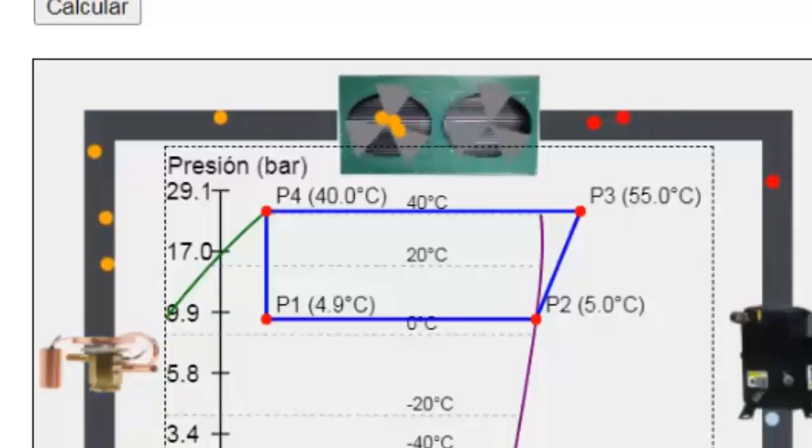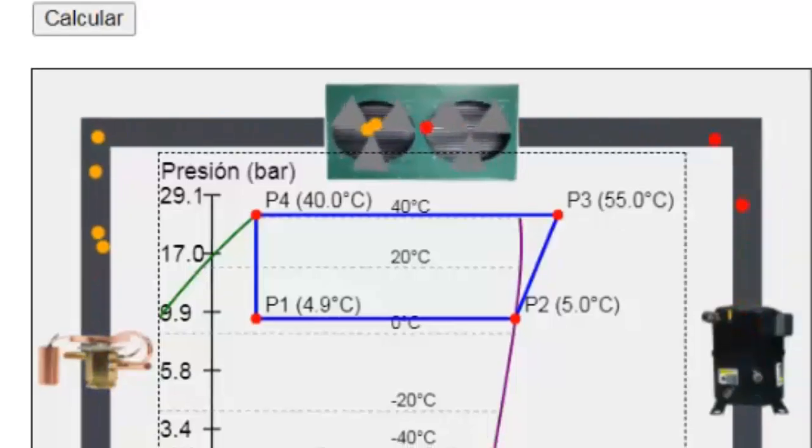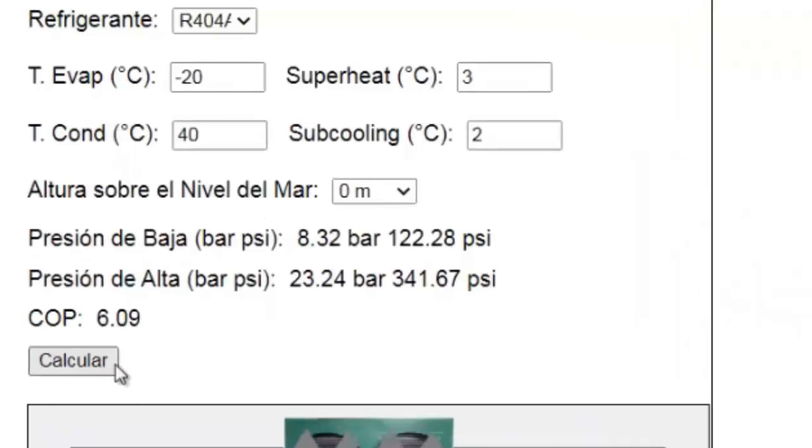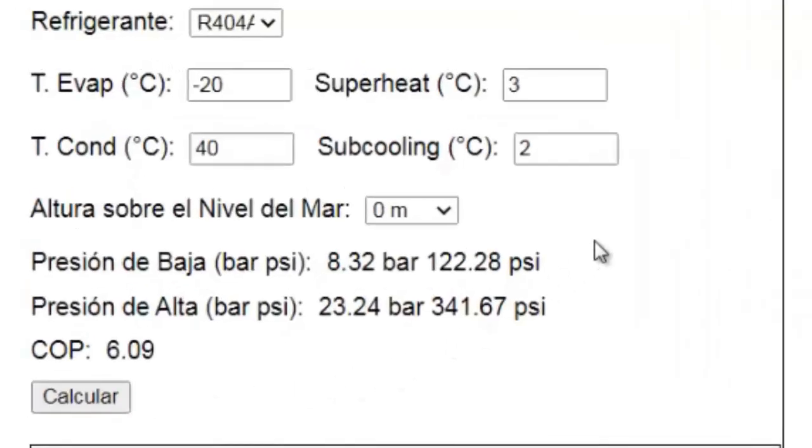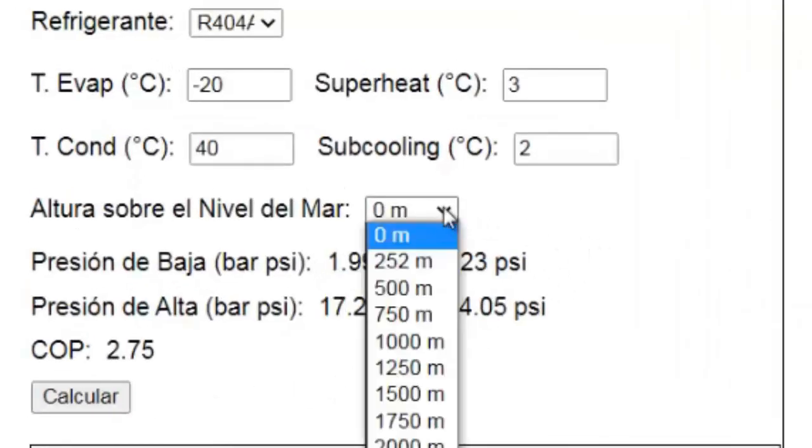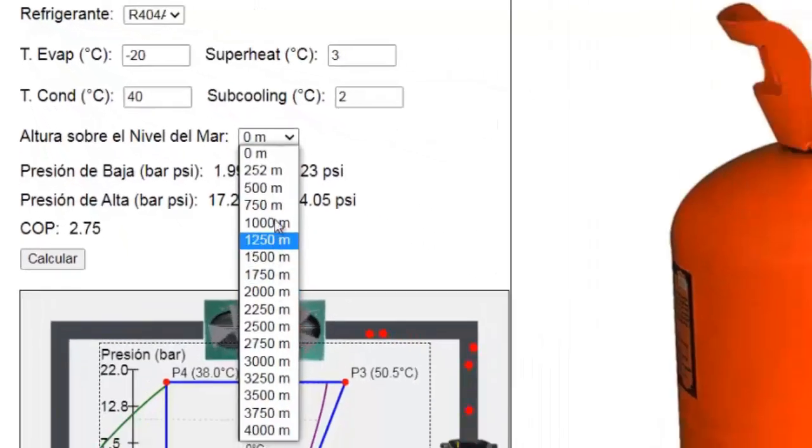The pressure indicated by the system's pressure gauge depends on the altitude above sea level. In this section of the simulator, we can select the altitude at which the equipment is located. This allows for a more accurate pressure gauge reading, which is crucial for high-precision refrigeration systems.